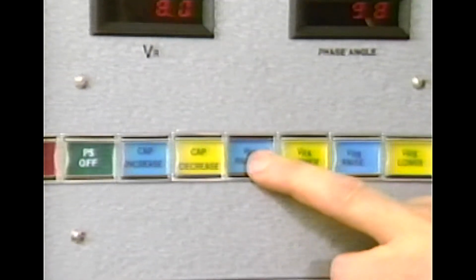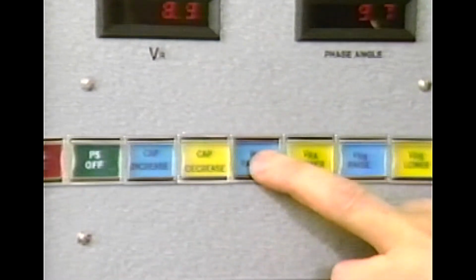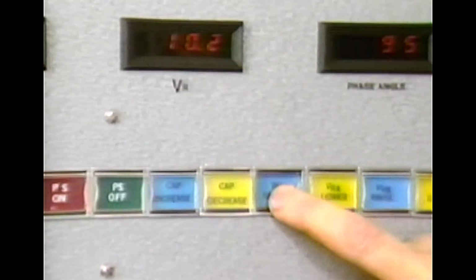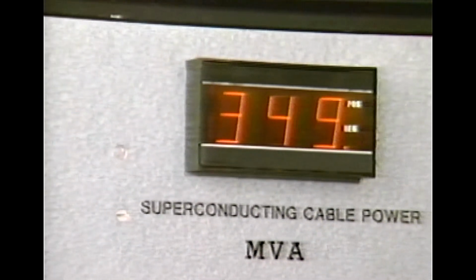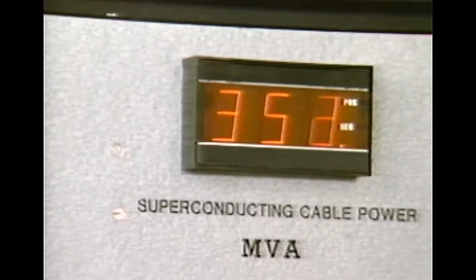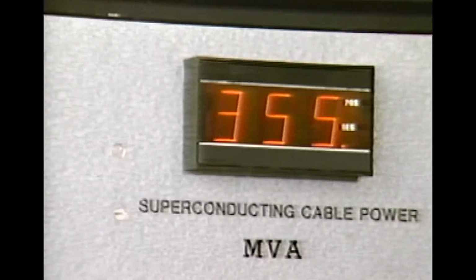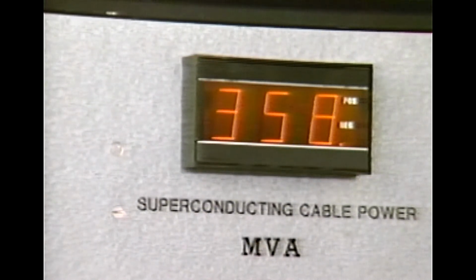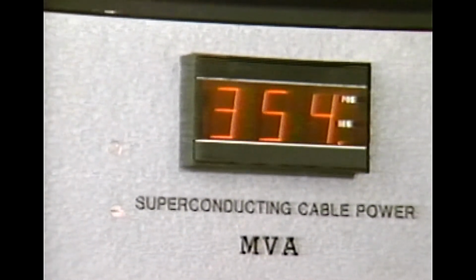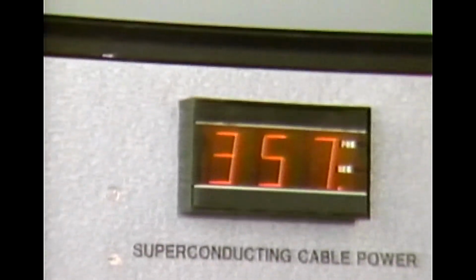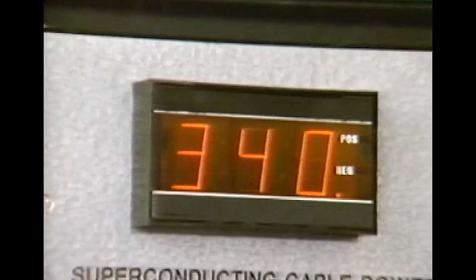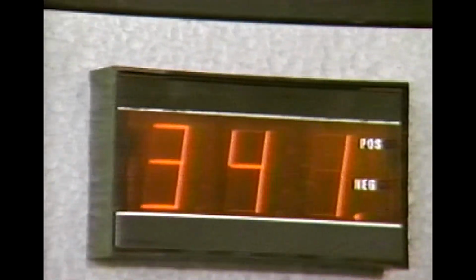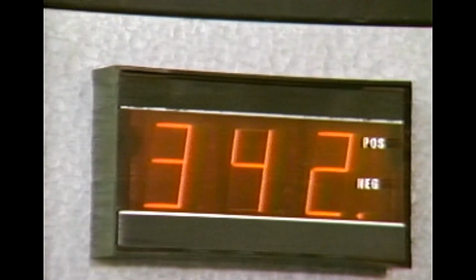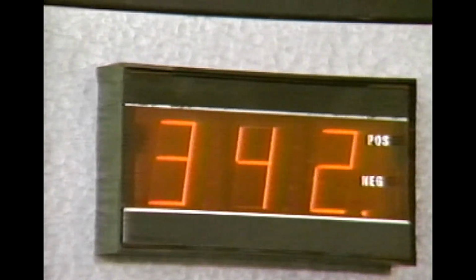Now at rated current. Cable unbalance is 26 amps falling. Amps, 19. Okay, that's good enough. We've got 7 amps of unbalance, 4,050 amps cable current, which if you could log that.